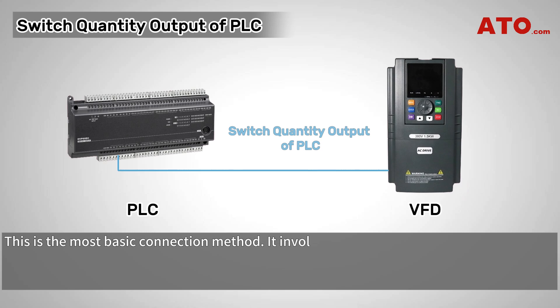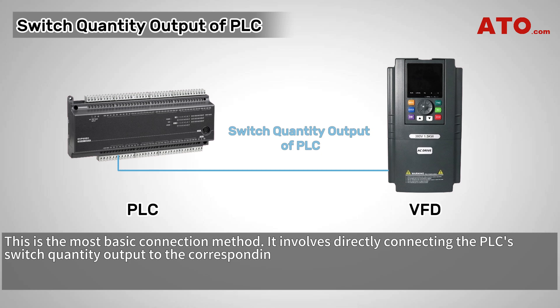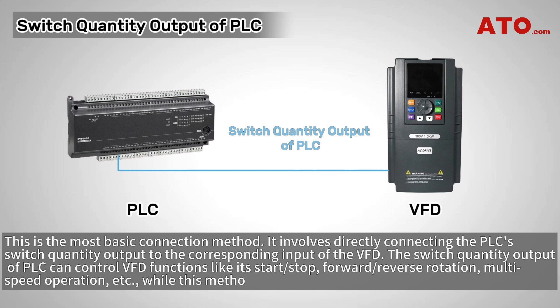Here are the general communication types between a PLC and a VFD. The first is Switch Quantity Output of PLC — this is the most basic connection method. It involves directly connecting the PLC's switch quantity output to the corresponding input of the VFD to control functions like start-stop, forward-reverse rotation, and multi-speed operation. While this method is not suitable for precise speed control.